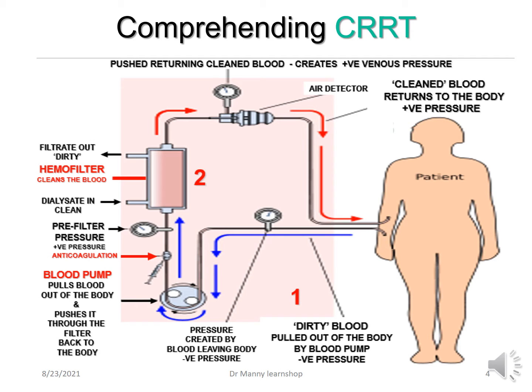Then the blood returns to the patient's body. However, before it does, it goes through or bypasses an air detector. Because if there's any air in the blood, you don't want it going into the patient and causing an air embolism. So the blood is pushed back, and this creates a positive venous pressure. When the blood goes into the patient, it's essentially cleaned of whatever you wanted to get rid of. And it has to be returned via a positive pressure. It has to be pushed back into the body. This is the CRRT circuit.